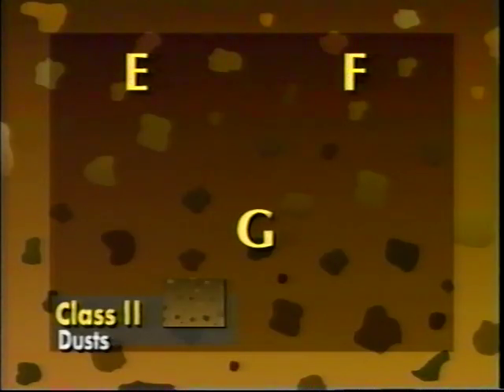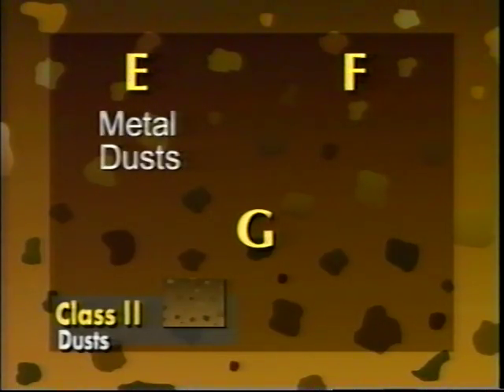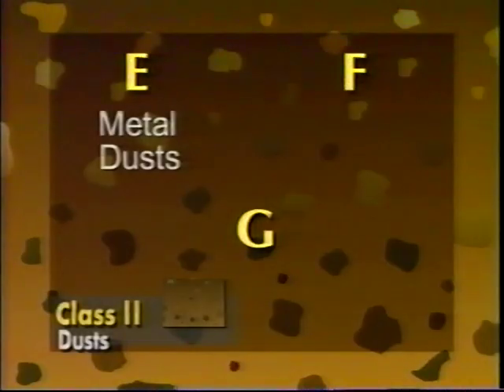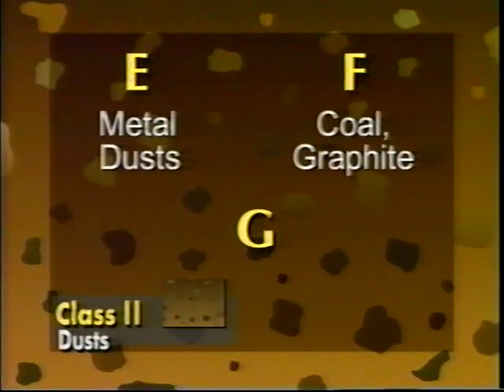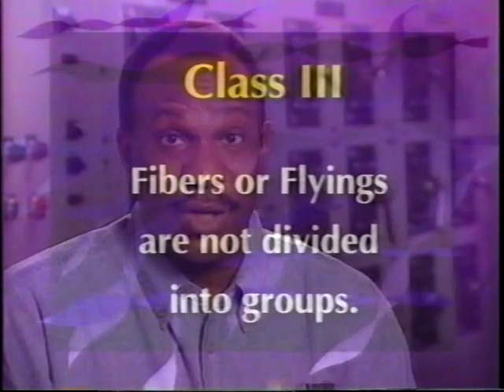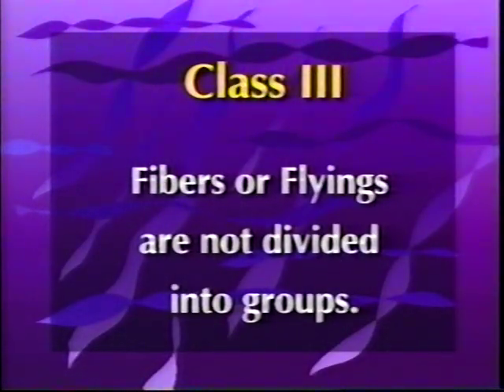For Class 2 dust, the groups are E, F, and G. Group E consists of metal dusts such as aluminum and magnesium, which can be electrically conductive. Because of this, Group E dusts are always considered Division 1, and they are the only Class 2 group that are Division 1. Group F consists of coal, graphite, and similar dusts. Group G consists of grain, plastic, and chemical dusts. For Class 3 fibers and flyings, the hazards are considered similar and aren't divided into groups.